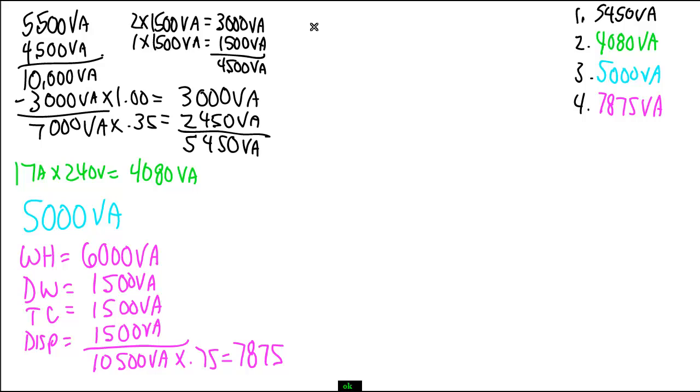So in this calculation, I'm going to have a 12 kilowatt or 12,000 watt range. If you look in column C, it shows us that if you have a piece of cooking equipment that is not over 12 kW, which I'm not over 12 kW, then I can use the demand factor that's right here. And if I look at the number of appliances, I have one, and I go all the way over to column C, I can see that I can use 8 kilowatts instead of the 12 kilowatts that I would normally use. So for number 5, I would have 12 kW, which really equals 8 kW.